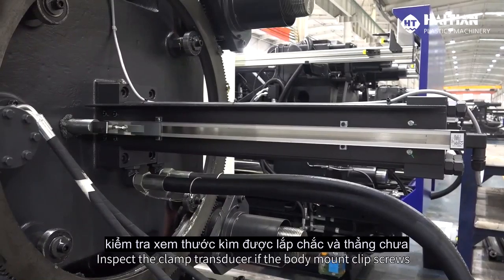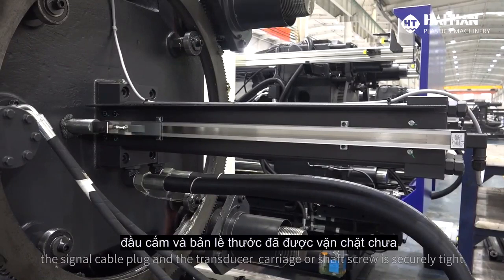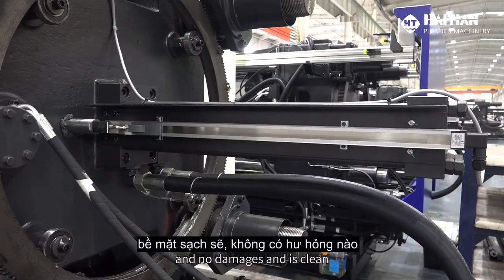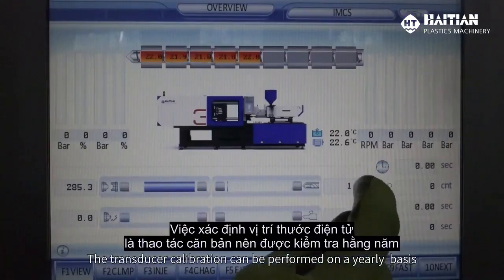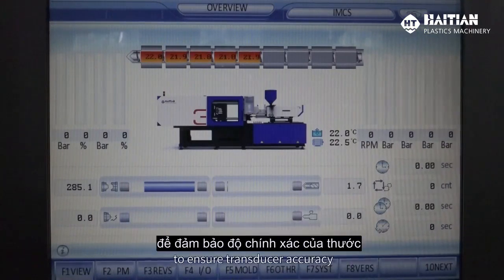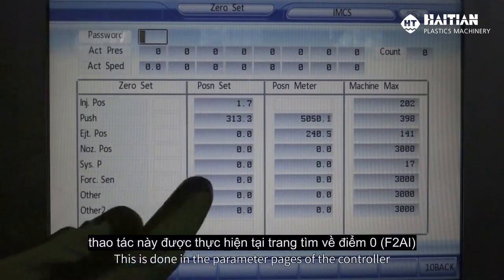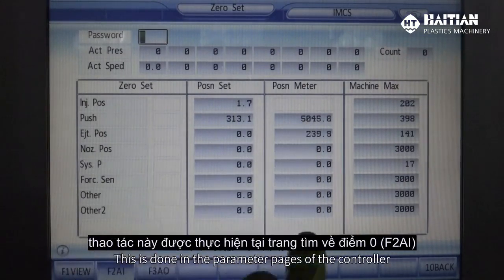Inspect the clamp transducer if the body mount clip screws, the signal cable plug and the transducer carriage or shaft is securely tight and no damages and is clean. The transducer calibration can be performed on a yearly basis to ensure the transducer accuracy. This is done in the parameters pages of the controller.